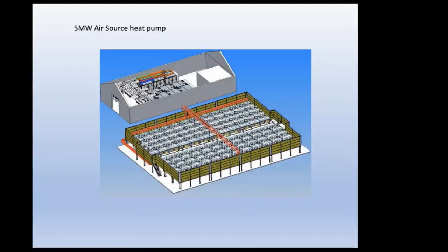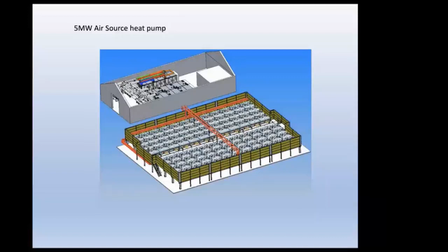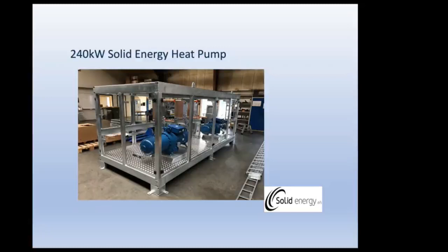That's what the 5 megawatt air source heat pump looks like. We can think about 2 tennis courts plus the building with the compressors in. So again, we're talking a lot of land. That is what a 240 kilowatt solid energy heat pump looks like. 2 compressors. That is twin stage. That would be able to raise water temperature up to 90 degrees. If it was just one compressor, we'd be going up to 65 degrees.